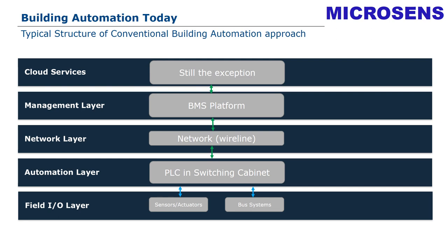All the sensors and actuators are connected by wire or by bus system directly to the automation layer, where the PLCs or DDC controllers are located, mostly mounted in cabinets. This layer is connected over the network with the management layer. Additionally, the network layer provides the complete network infrastructure for building automation systems, which allows connecting and networking all the PLCs, and provides data transfer from the automation layer to the management layer, where the common BMS platform resides.